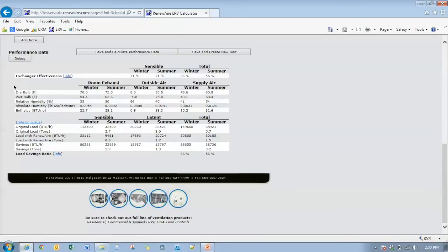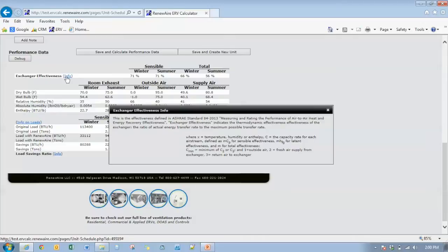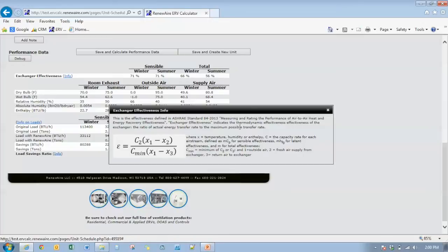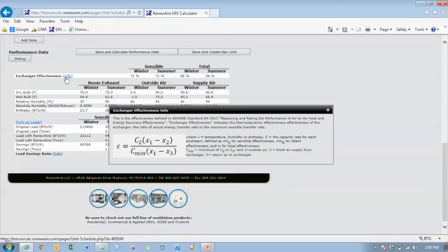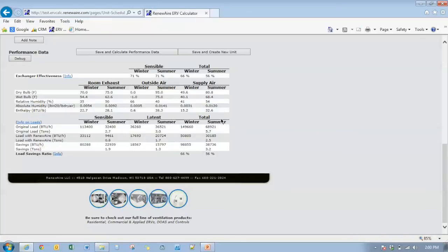This is where the changes of effectiveness show up. We have exchanger effectiveness is the thermodynamic effectiveness of the energy exchange core and that's defined by ASHRAE 84. This is the capability of the energy exchange core to transfer energy. It does not necessarily matter which airstream it is transferring the energy. It's the ability of the core to transfer energy in either airstream. Click out of that calculation. You can see here, okay, so we have exchanger effectiveness up here.